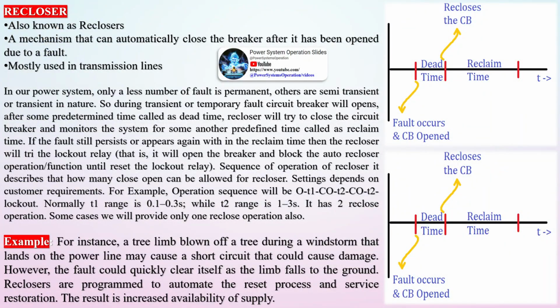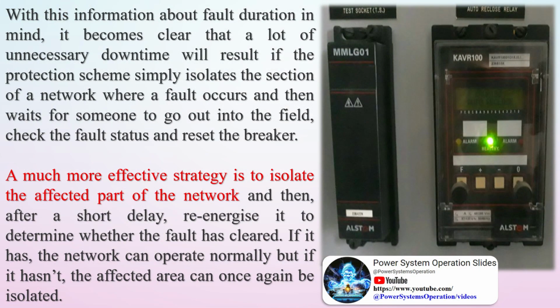In principle at least, it's a simple device. Essentially, it comprises a circuit breaker with associated protection relays, a mechanism that will allow it to be closed automatically after a trip, and a controller that provides the auto-reclose functionality. The ANSI standard device number for the controller is 79. Typically, the complete assembly is installed at the top of one of the poles or towers used to support the power lines. Relay parameters: action time.